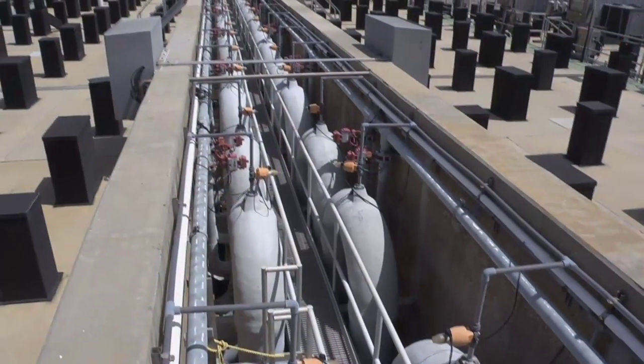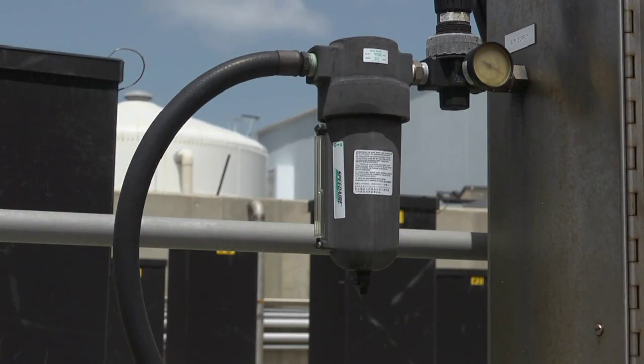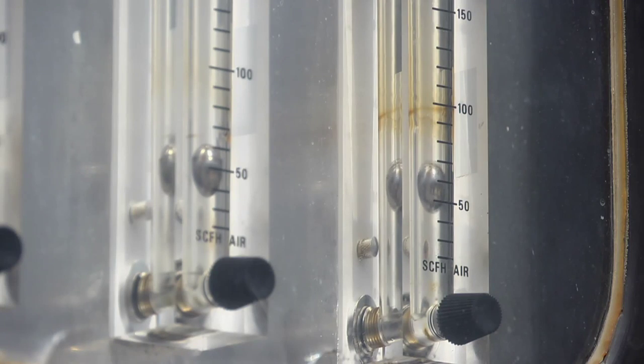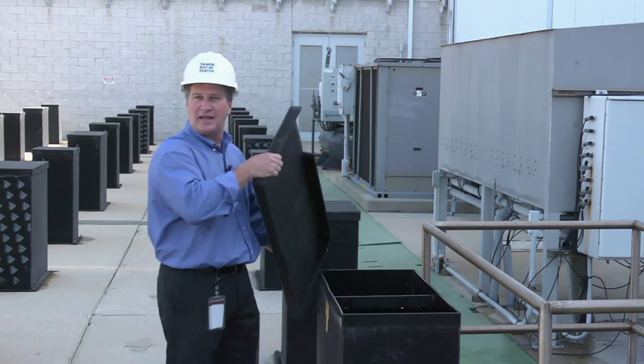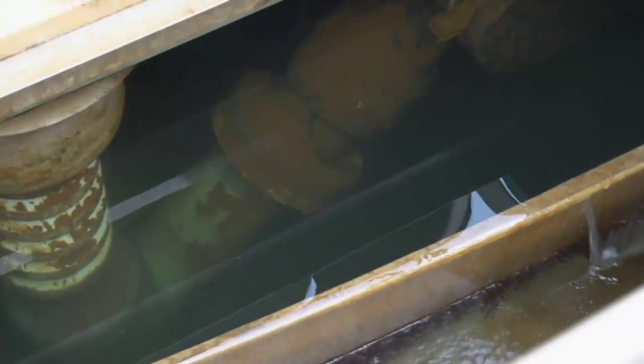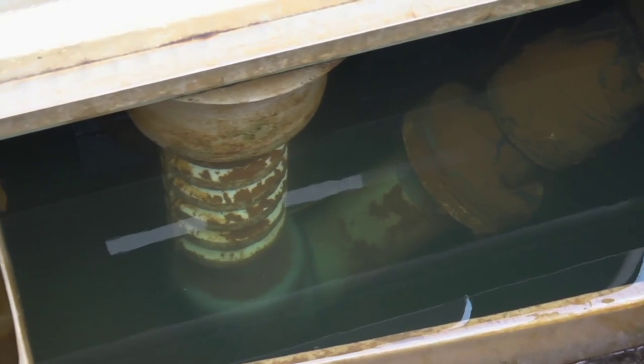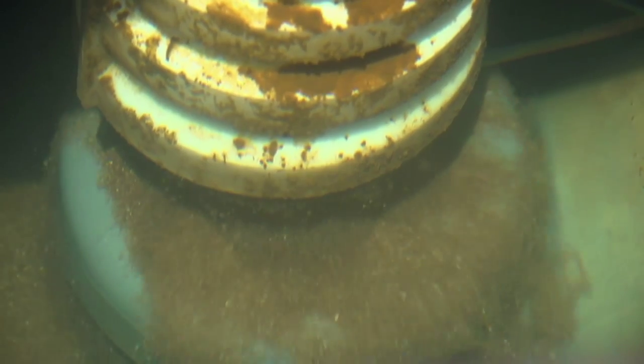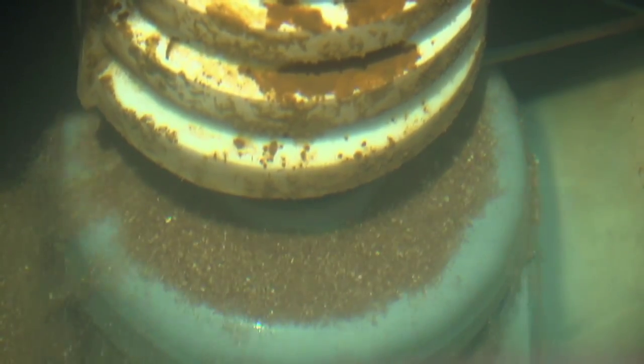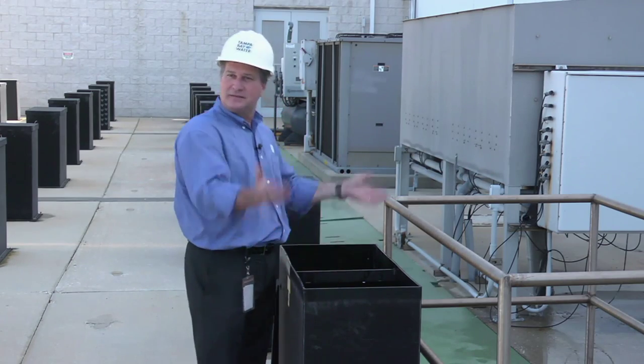The salt water now goes through sand filters to remove larger particles. The sand is rotated by air, and dirty particles attach themselves to the sand. One of the neat things about this is we don't have to shut any of the filters down to backwash them — they continuously clean themselves as they're working. You'll see the sand being thrown up against the sides; the dirty water comes off the sand particles, gets collected, and the clean sand goes right back in and does more cleaning.